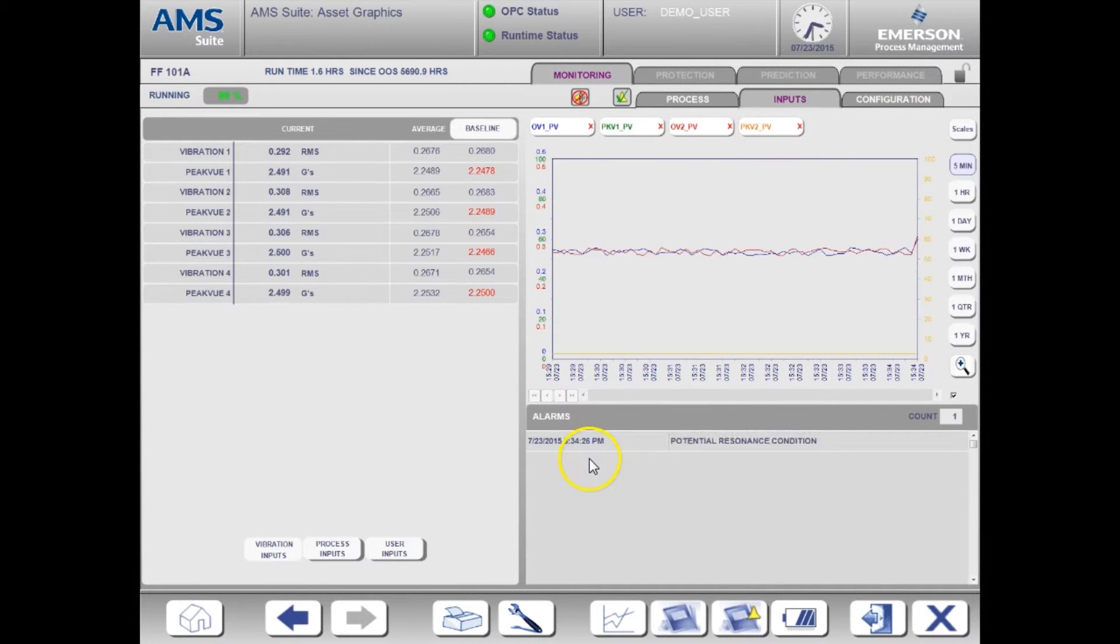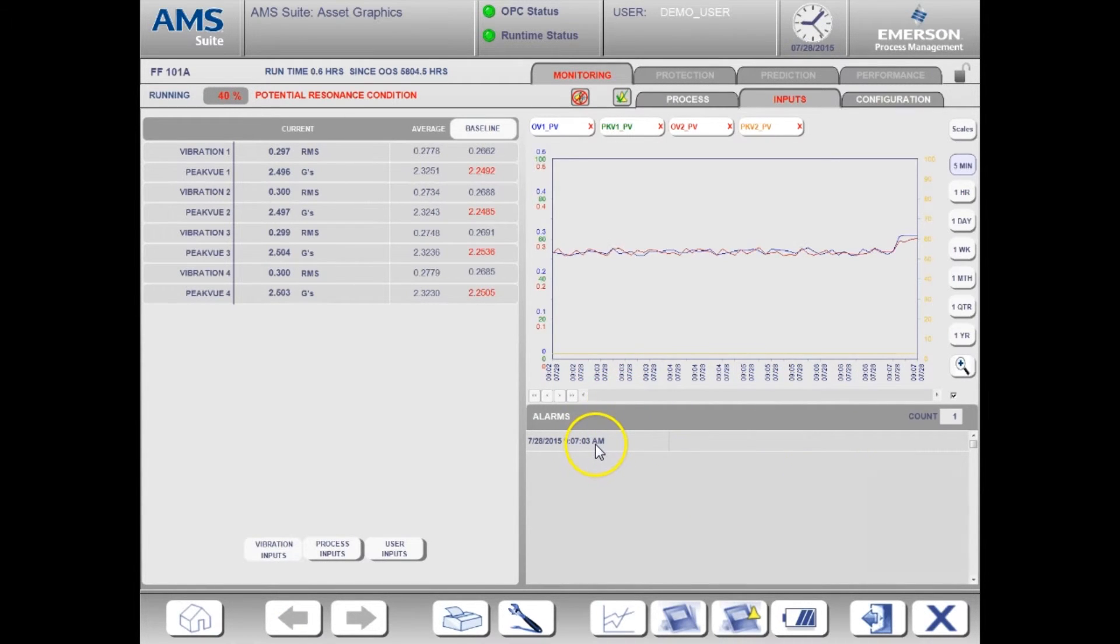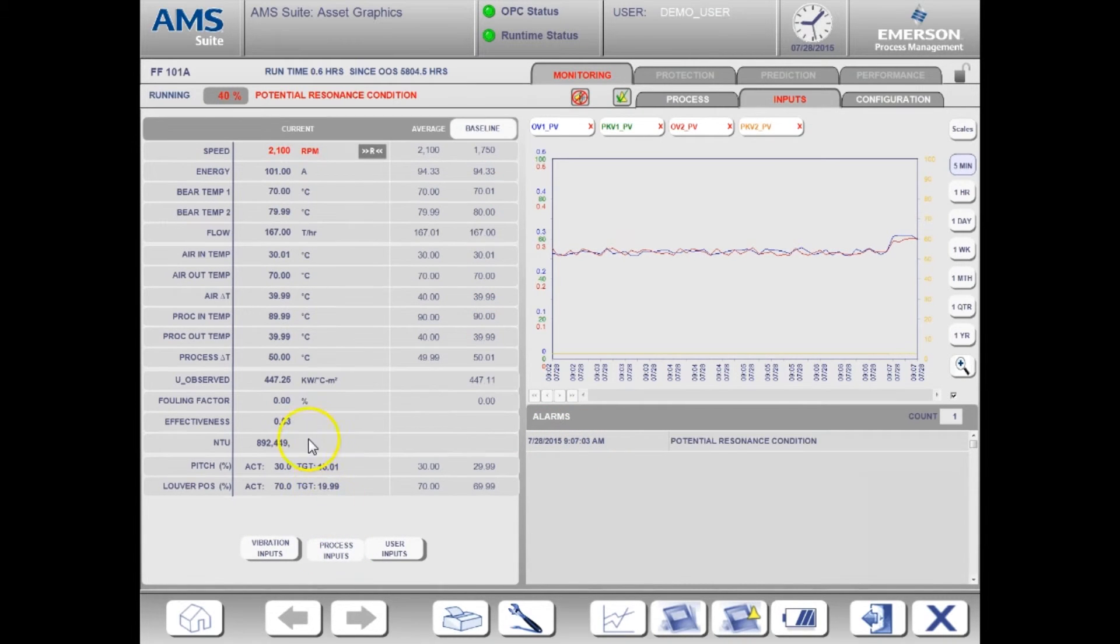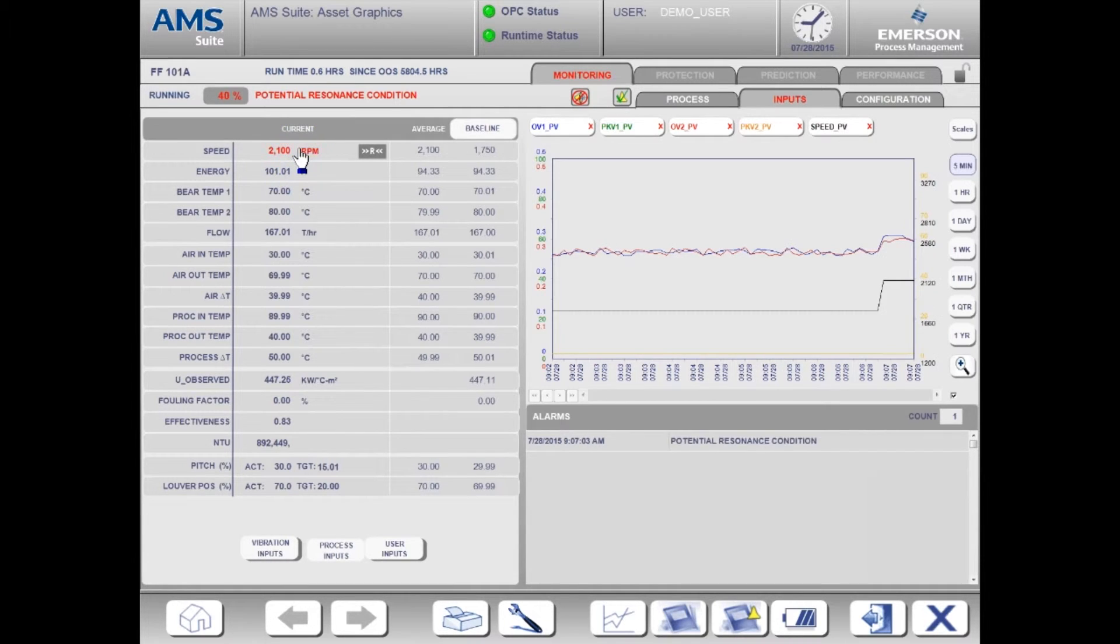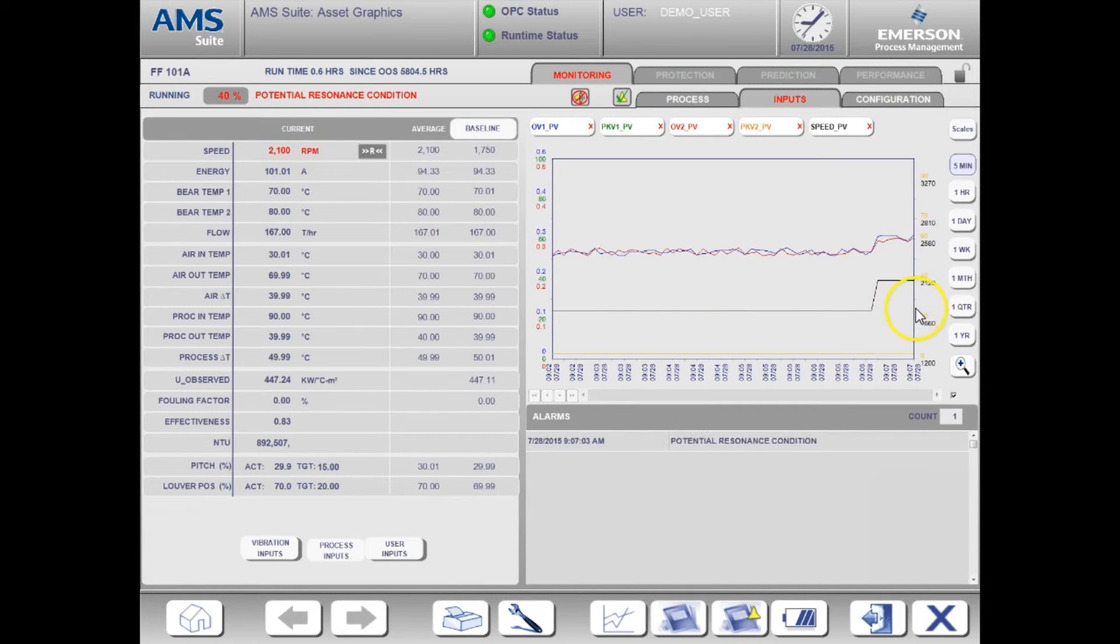The active alert is now for potential resonance condition. This is a warning alarm. To understand what triggered this alert, I'm going to add one more value to the trend. This time I'm going to add the speed. The reason I am looking at this value is because there are known resonance frequencies for the fan's motor. By looking at the speed, we can determine if we are operating in the known resonance bands.